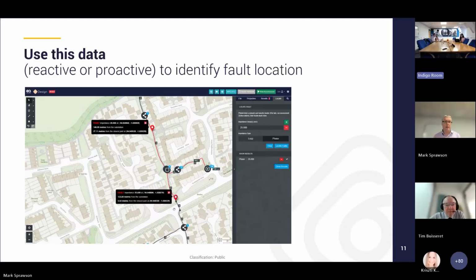Because the network splits, it comes out from the substation shown on the right-hand side of this video. So you might think, okay, you've got two choices now, where do you go? And the answer is the system pulls up not just the location in terms of how far it is from the substation, but clearly it also pulls up how far it is from the closest joint. And hopefully you can see it says on the top one, 27 meters from the nearest joint, and on the bottom one, it's 42 centimeters. And experience has shown us, and I'm sure you will have seen similar, that over 90% of faults occur in joints, not in the main sections of cables. So the engineers go to the one which is closest to the joint.